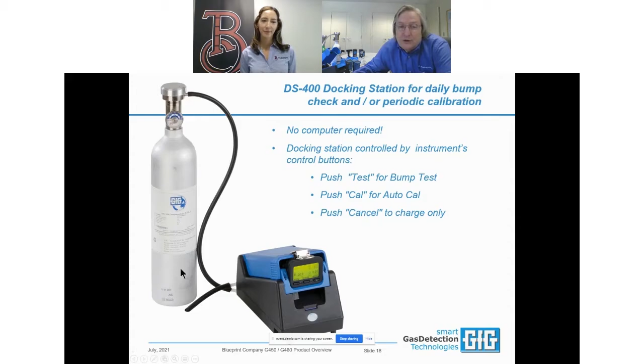And when you've got an instrument that can measure 7 different kinds of gases at the same time, that's kind of handy. Each of these inlets can be programmed for use with multi-component mixtures, depending on what kind of sensors and what kind of gas that you need to use. Your 4 cylinders of gas actually exceed the 7 channels of detection that you can get into the instrument at the same time. And the beauty of the docking station is it not only automates your test and calibration procedures, but it also automates your record keeping functions.